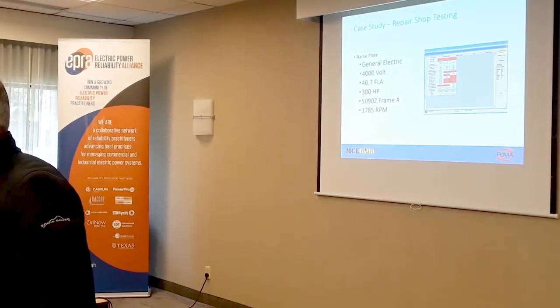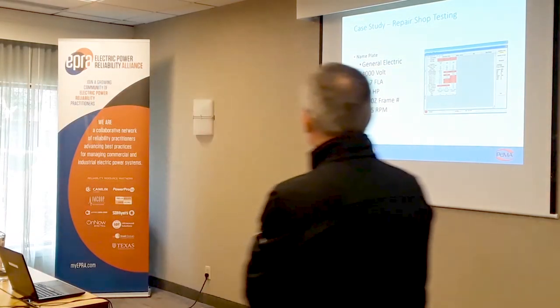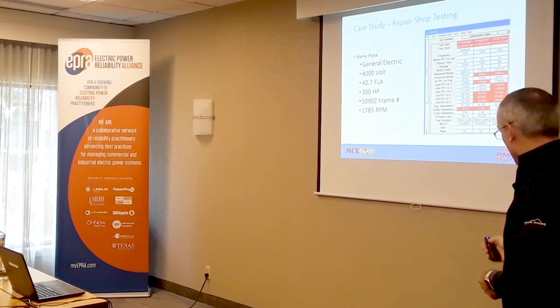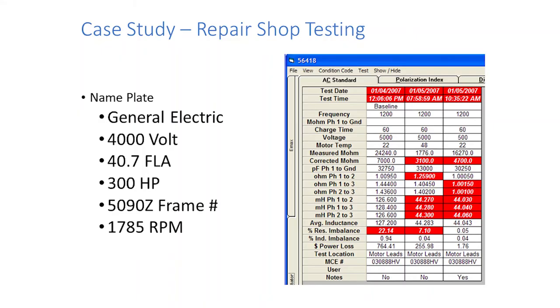Let's apply the trifecta into some of these fault zones. Put yourself in this situation: you just sent a motor to Joliet Electric for repair. You're hoping they're testing it with technology — digital low resistance ohm meters, surge tests, high-pot tests — they have a variety in their shops. In this situation, the resistive imbalance is 22%. Ideally the shop is applying some type of low resistance ohm meter and saying: 22% — unacceptable, not even close to acceptable.